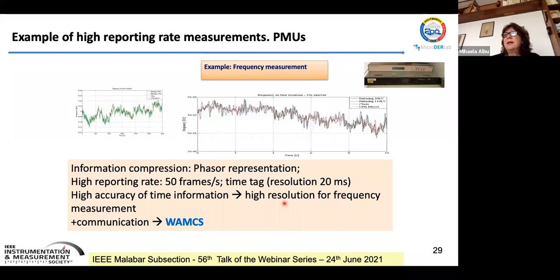We will not speak in detail about phasor measurement units because they are used in wide area measurement and control systems for controlling large systems. However, until recently, they were the only measurement equipment providing high reporting rate information, every 20 milliseconds, yes aggregated because it's RMS, on what happens with voltages and currents at a specific node.